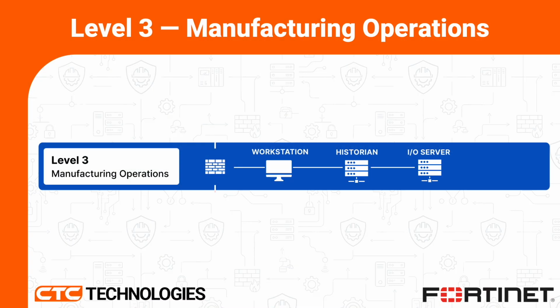Moving on to level 3, this is our manufacturing operations level. This is really where the boundary between IT and OT begins. At level 3, this is where we have our MDFs, our IDFs, our user workstations out on the floors, maybe where the plant manager's computer is, but more geared towards the OT space. This is where our controllers and operators sit, connecting onto their workstations to connect to SCADA systems and historians, the journals, things like that, to read coils and write functions down to our PLCs and RTUs.